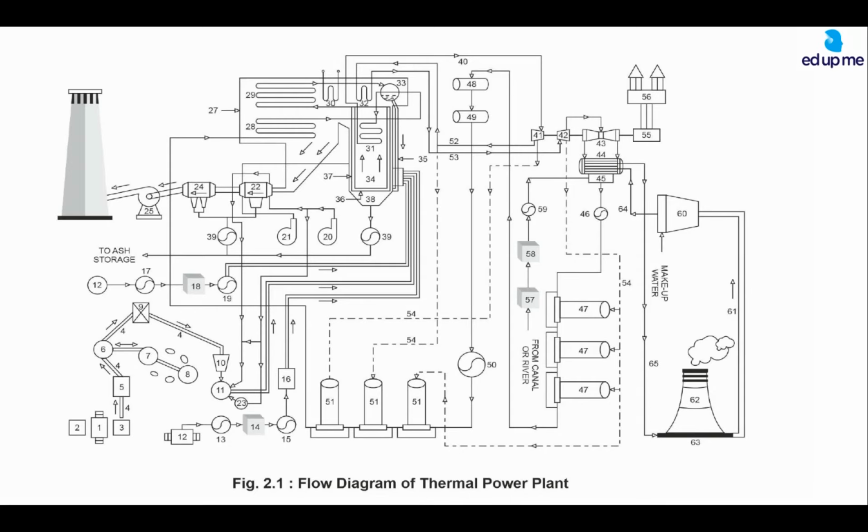So this is cool air, but some part of the air will pass through the air preheater, and from the air preheater it will be heated. Here it will be mixed. So there is going to be a cold and hot air mixture here. And there is a damper, right? So there is a door kind of thing, and that door will be opened or closed partially in such a way that you decide how much cold and hot air to convey to the coal mill. That you have to decide depending upon the load on the boiler, the load on the power plant, right?